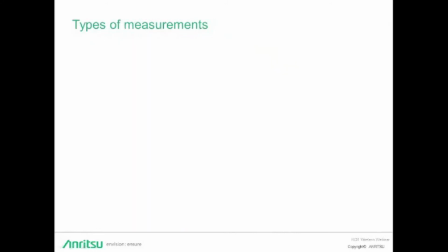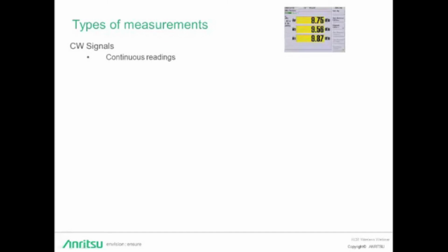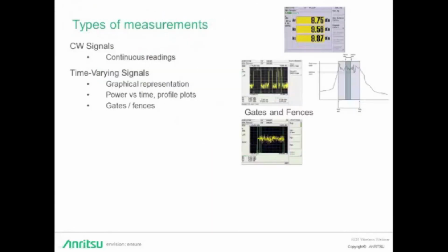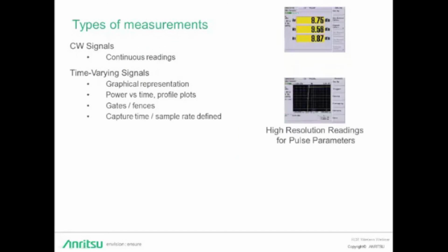So, regardless of being standalone or integrated with the sensor, power meters offer a wide variety of features and functionality. For CW signals, where timing isn't critical, one may just want continuous readings. For time-varying signals, one may want a graphical representation of the power with things like power versus time or profile plots. With that, you can do things like set limit lines. One can set up measurements to only measure power within gates and exclude fenced regions. Users can change the capture time.